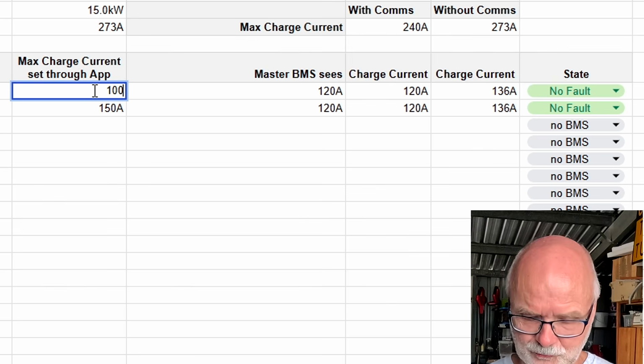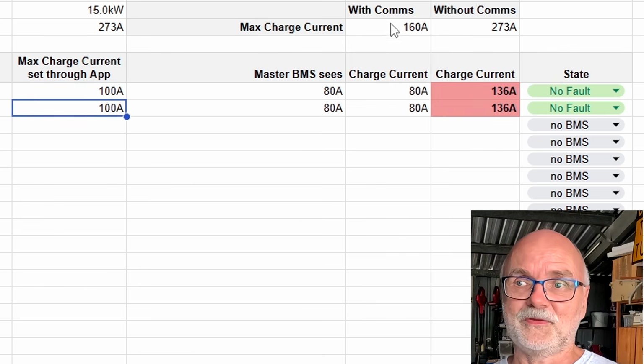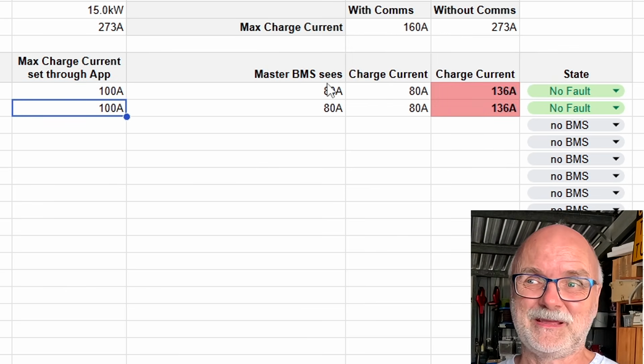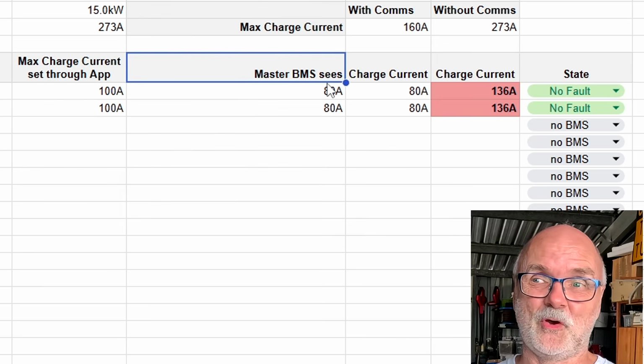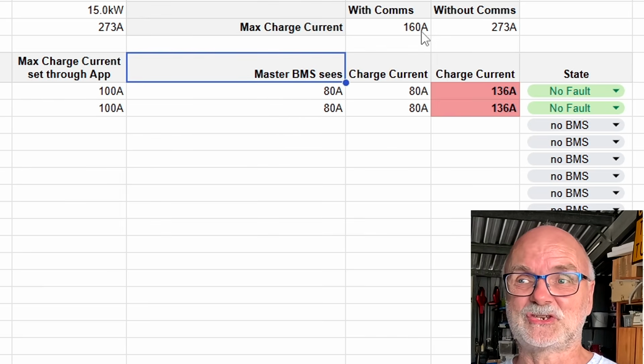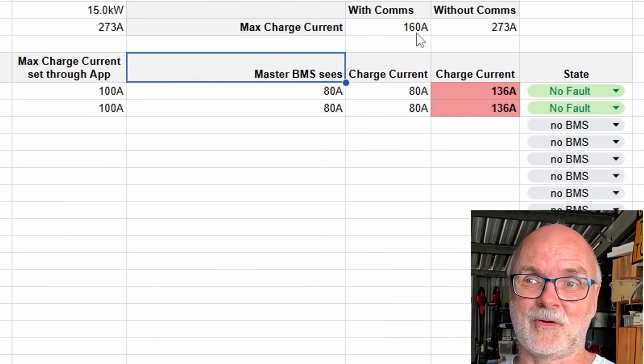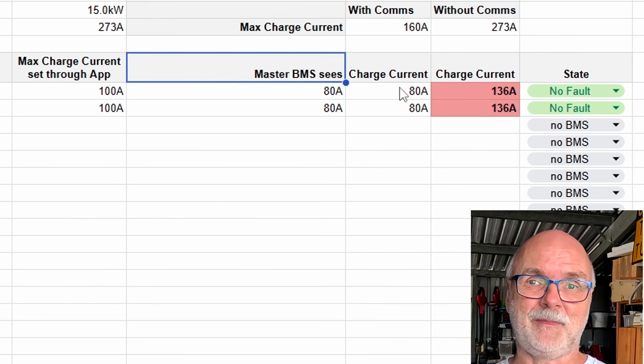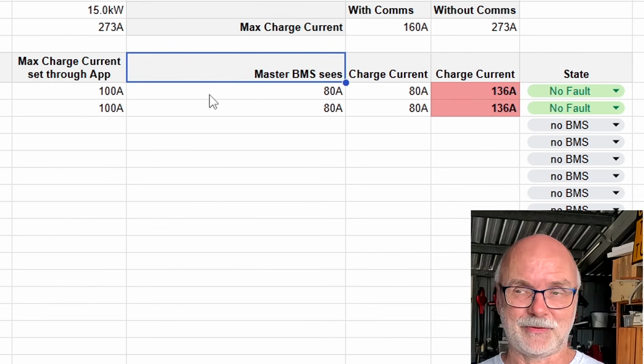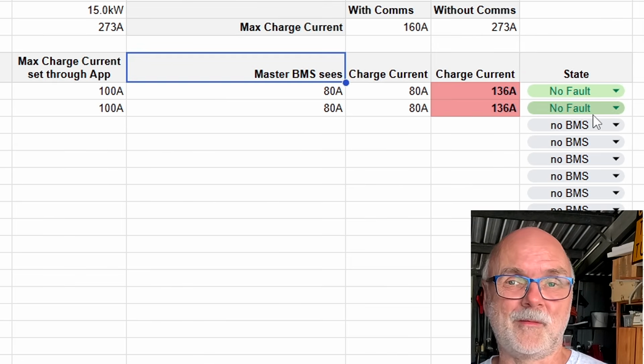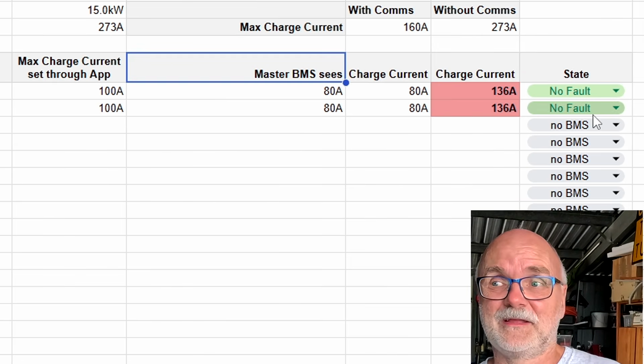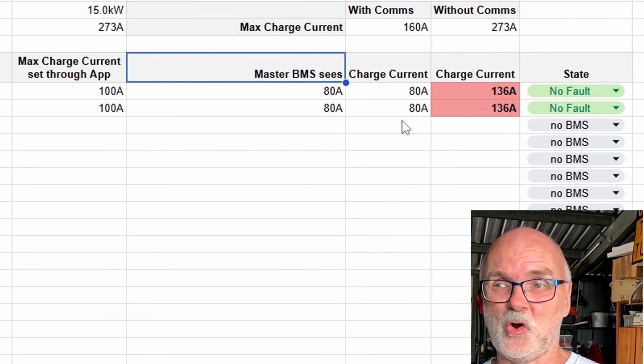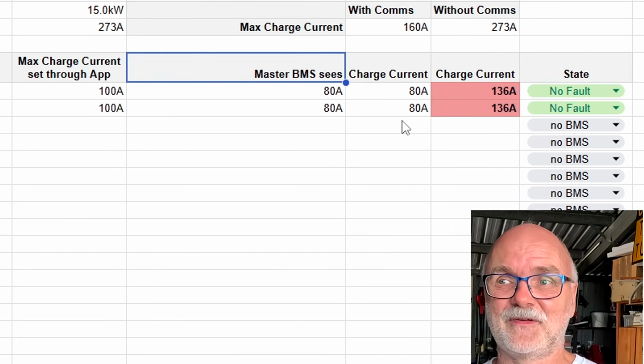But if we go back to 100 amps, with the communication, it doesn't matter because the BMS communicates to the inverter and says, hey, I can only charge with 160 amps maximum. You can deliver 270, but please only charge me with 160. That's 80 amps into each of the batteries, exactly as you have set it up. And then it doesn't matter if 1 or more BMSs go into fault. The communication will always ensure you are staying safe. It is like an extra layer of safety.